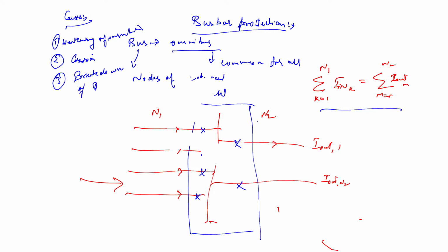Breakdown of insulation can be due to over voltages, foreign objects and so on. Also, rodents, lizards and snakes are known to have caused busbar faults in remote unmanned substations.